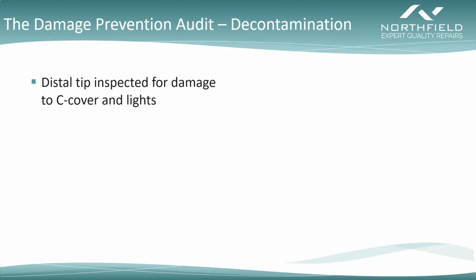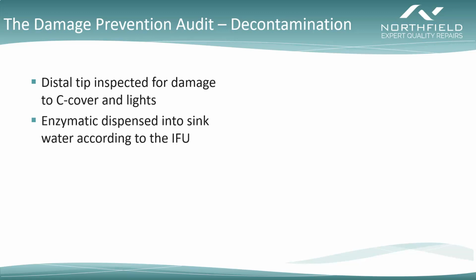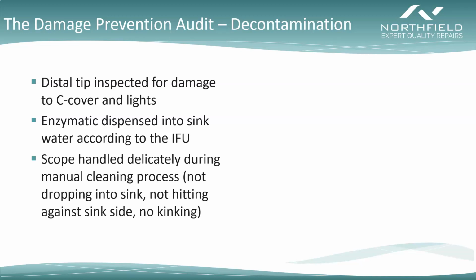Next, during the decontamination phase, we want to inspect that distal tip for damage to the C cover and the lights. We want to make sure that enzymatic is being dispensed into the sink water according to the IFUs. We very often see technicians putting too much enzymatic into the sink because the assumption is that more detergent will make it more clean, right? And that's just simply not true. It actually tends to inhibit the cleaning process, especially when we come to the high-level disinfection. And then we also want to make sure that the scope is handled delicately during the manual cleaning process. So not dropping into the sink, not hitting it against the sink side, no kinking.